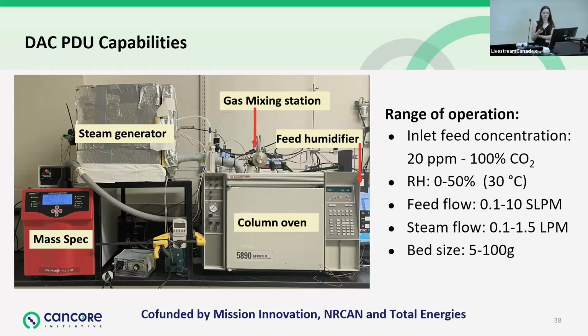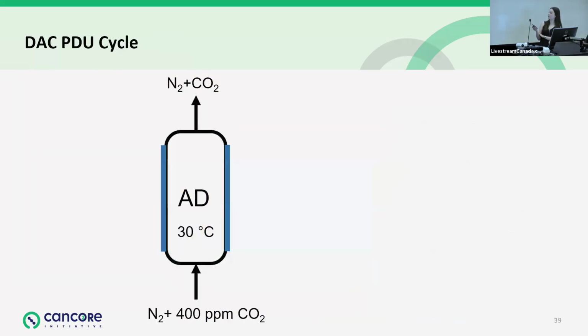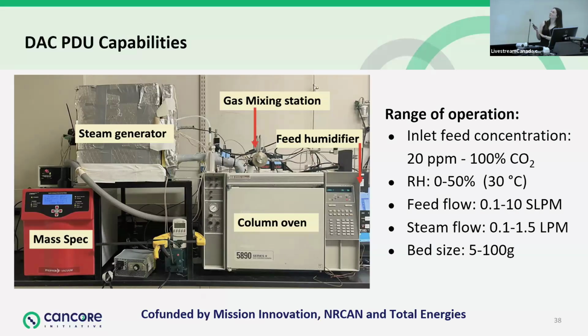The range of operation that we can currently do is an inlet feed concentration between 20 ppm and 100% of CO2 dry. What I will note is that the mass spec, unlike our FID methanizer that I previously talked about, has a baseline at the sampling frequency that we need of about 20 ppm. So we can't really see anything below 20 ppm, so that's the one thing that the micro DCB that I showed before is much more sensitive to, at its like 0.1 ppm range.